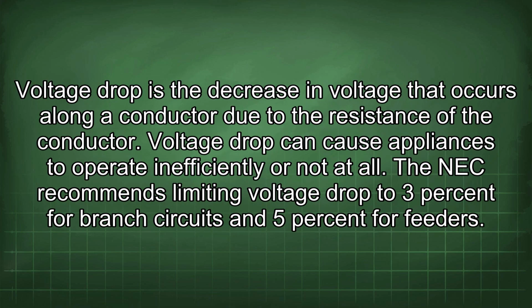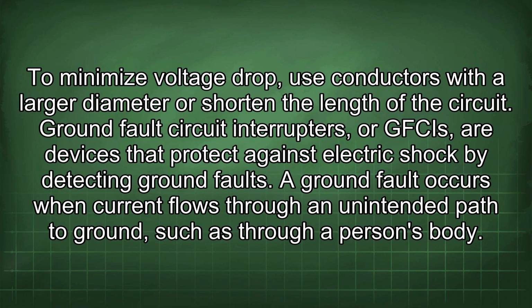Voltage drop is the decrease in voltage that occurs along a conductor due to the resistance of the conductor. Voltage drop can cause appliances to operate inefficiently or not at all. The NEC recommends limiting voltage drop to 3% for branch circuits and 5% for feeders. To minimize voltage drop, use conductors with a larger diameter or shorten the length of the circuit.